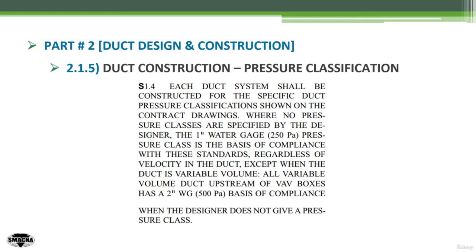Starting with the first step in the duct construction process, which is to determine the duct pressure classification. Quoting from SMACNA: each duct system shall be constructed for the specific duct pressure classification shown on the contract drawings. Where no pressure classifications are specified by the designer, the one-inch water gauge or 250 Pascal pressure classification is the basis of compliance with these standards, regardless of the velocity in the duct.